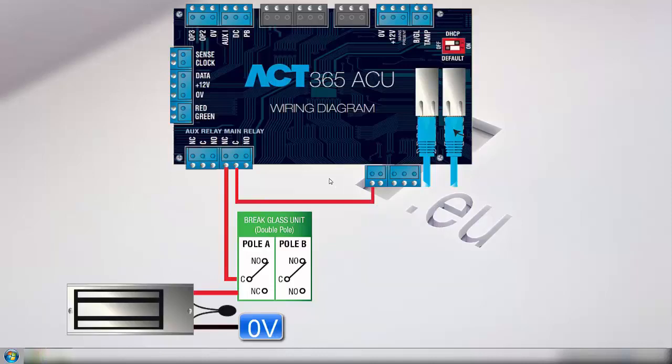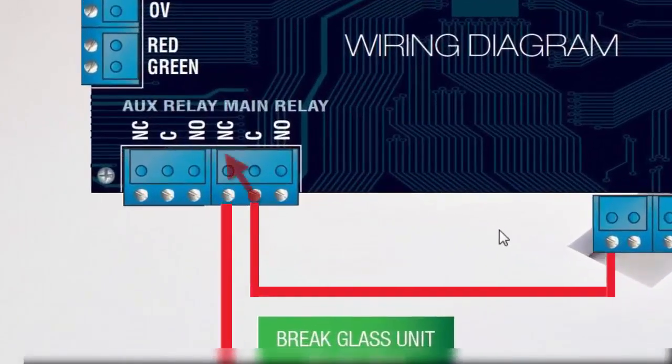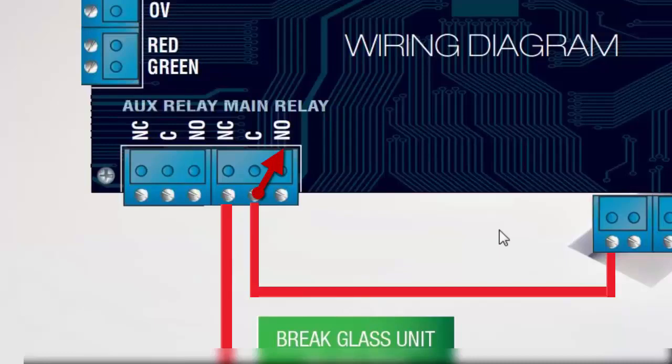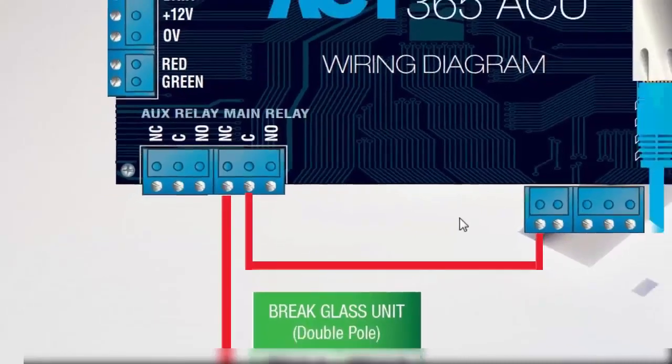In its normal state there is continuity or a connection between common and normally closed. When the relay is energized it swaps state and the armature connects common and normally open, breaking the connection between common and normally closed. The break glass uses the same principle.